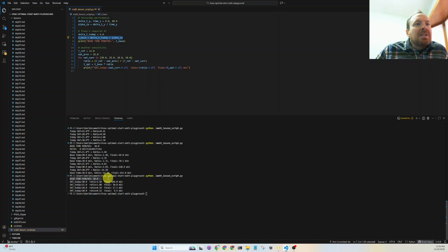So our base minute calculation is off of our ordinary degree per minute, and then we're factoring in some weather data, because the outside air weather can have drastic effects on the building getting warm or cool in the middle of the night when the HVAC is off.